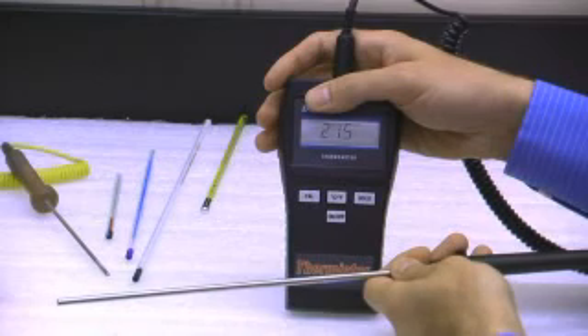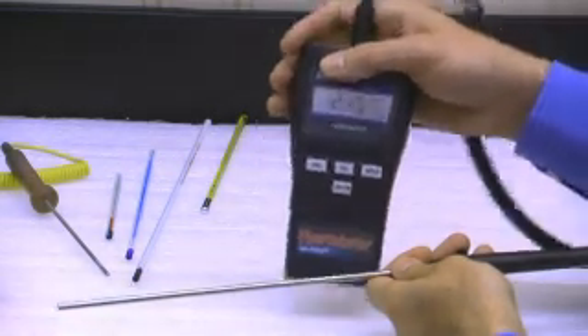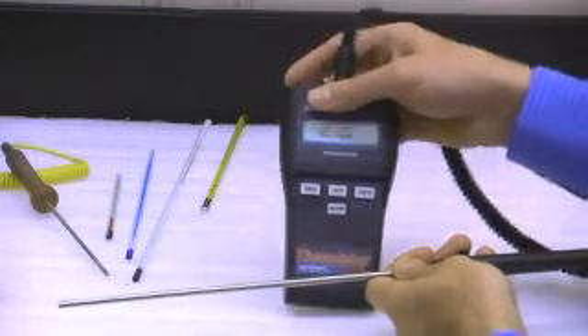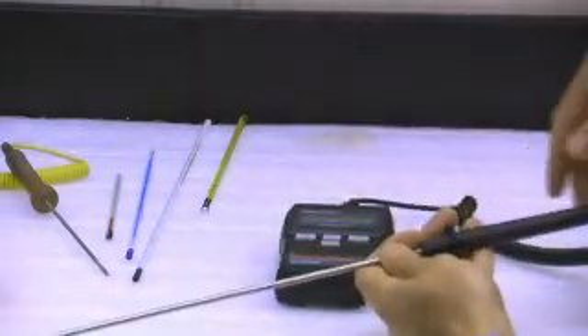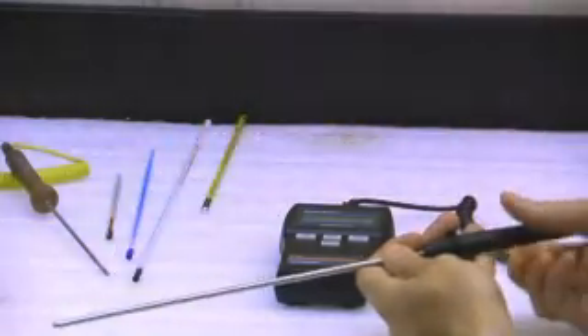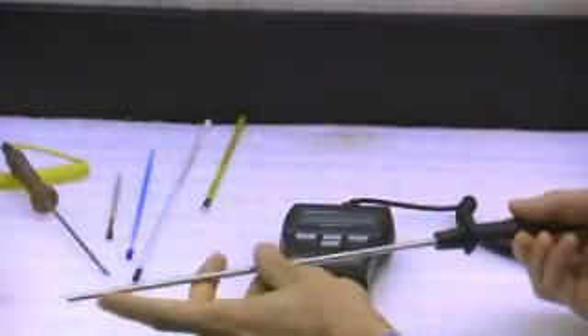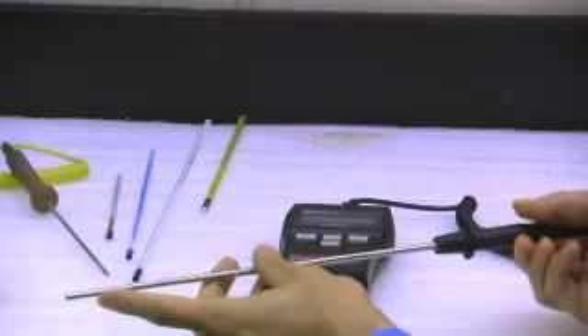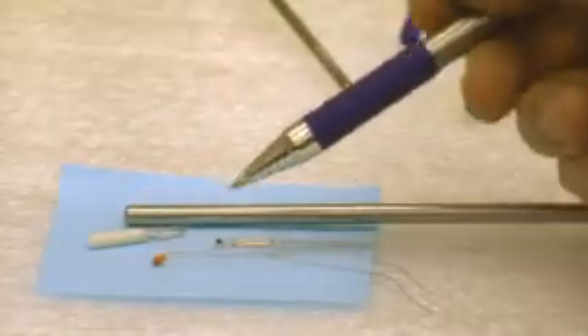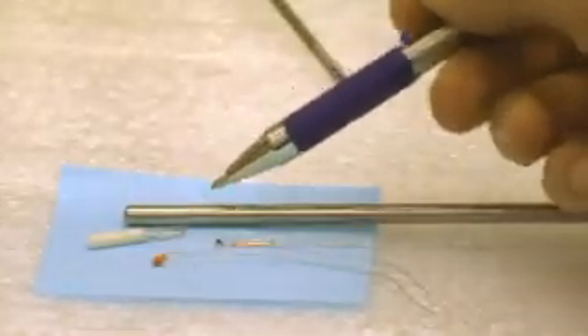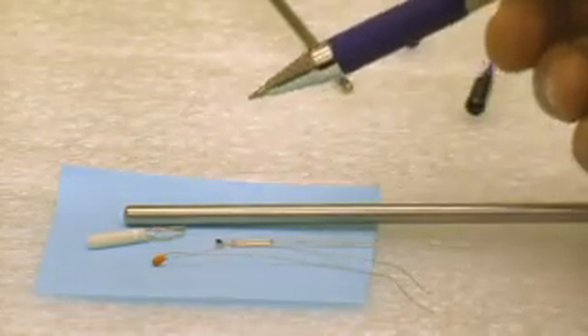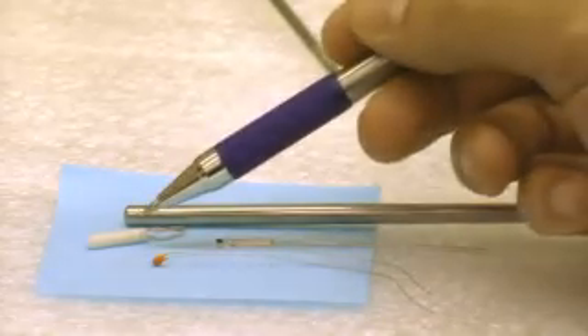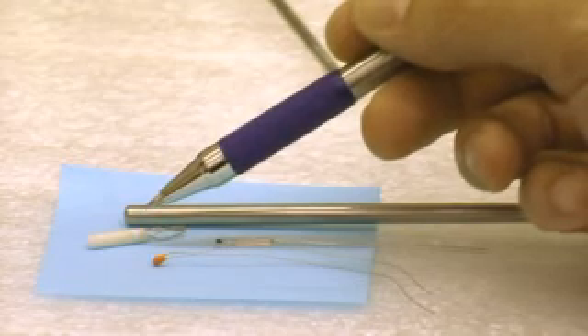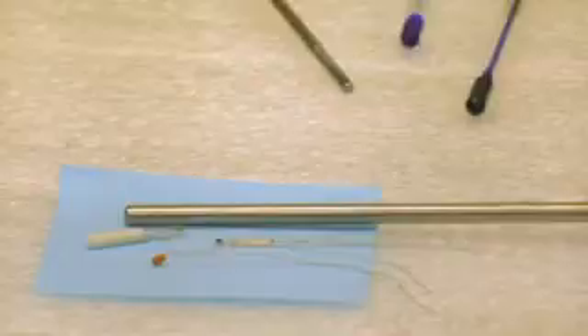Here's an example of a digital thermometer. It has three components. There's the readout with a digital indication. There's a probe that comes with it. And then inside the probe, there's a sensor. Here are three examples of sensors that would be inside a probe of this geometry. Each of these sensors is a resistance sensor. The resistance varies with temperature, and that's what the readout detects.